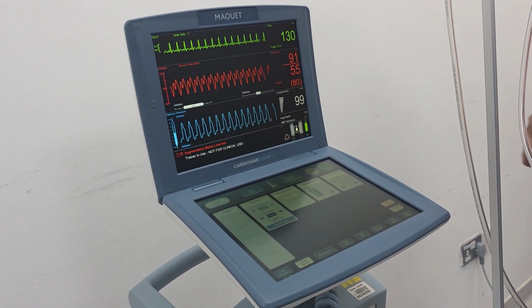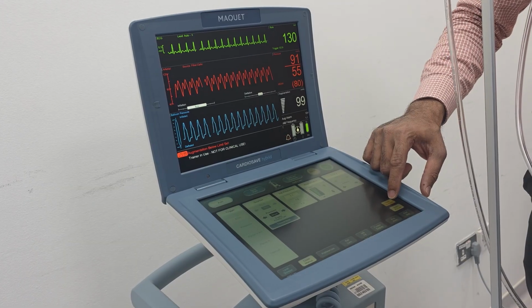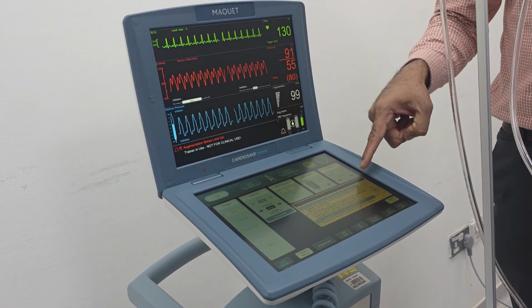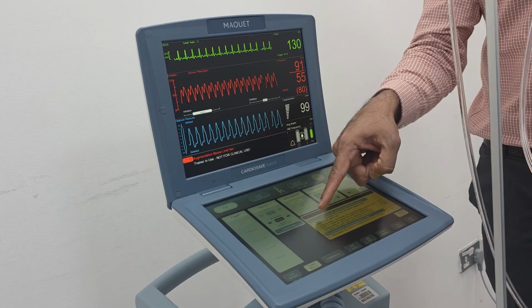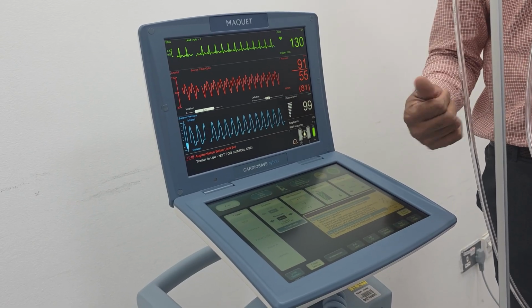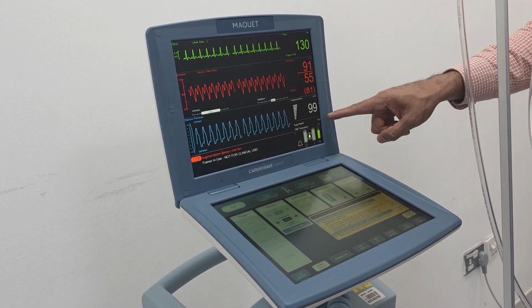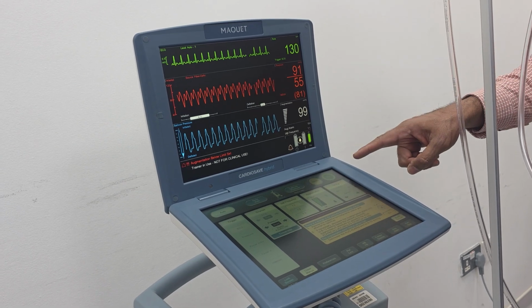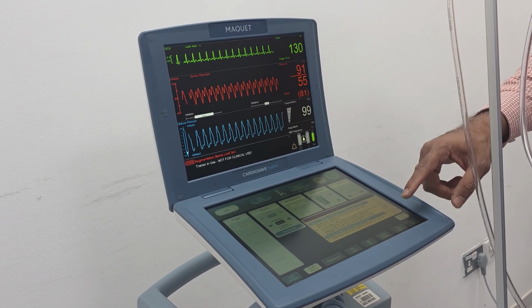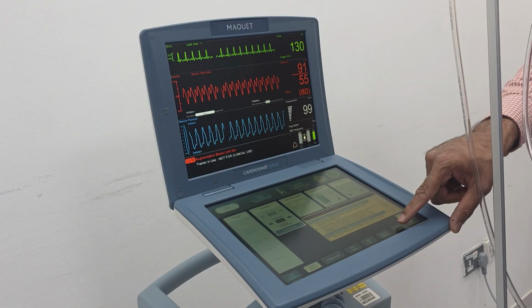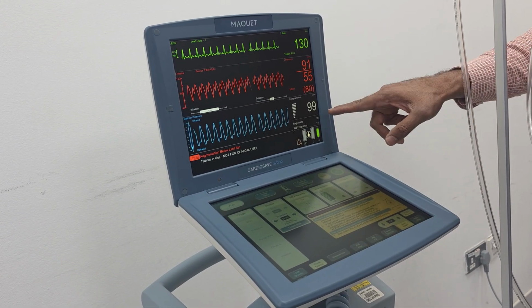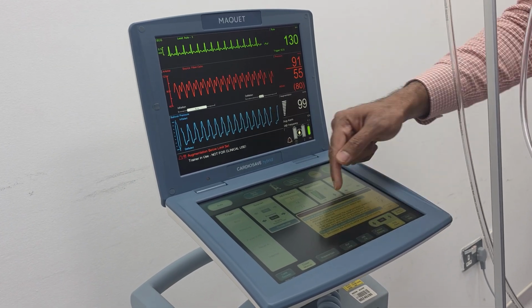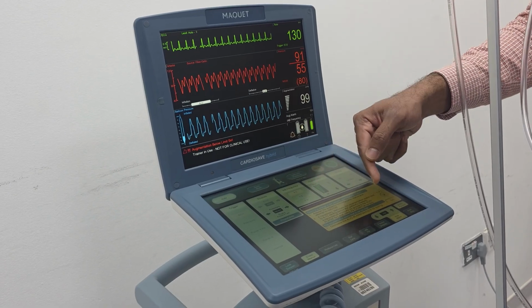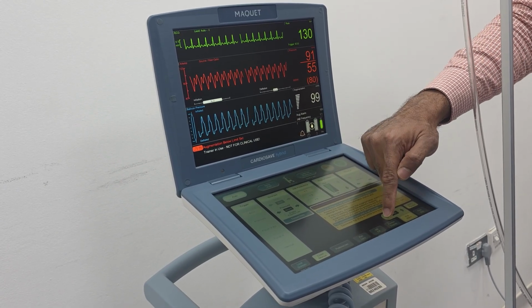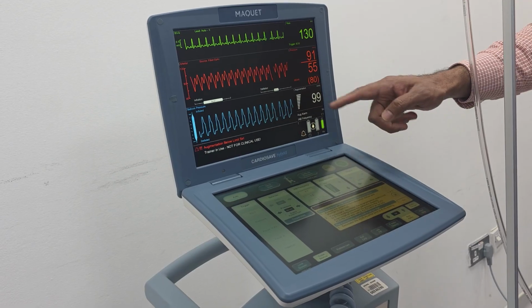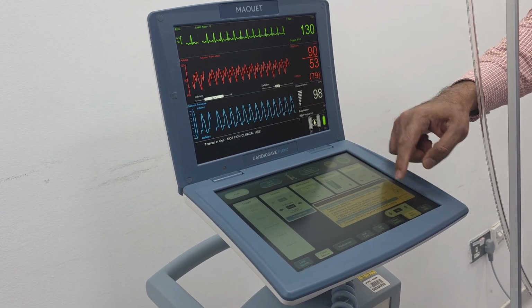But whenever you are facing an alarm, if you need more information, go to the help button. There is a change in patient hemodynamics. So it will give you an indication how to set. Okay, so it is asking you to reset the alarm, but you need to look into the clinical condition later on. But to mute this alarm, same like CS300, we have the augmentation alarm. Press augmentation, selected. There is up and down arrow. So it's recommending 8 or 10 mmHg below the current value. You can reduce. It was 99. Let's go to 90. Set.